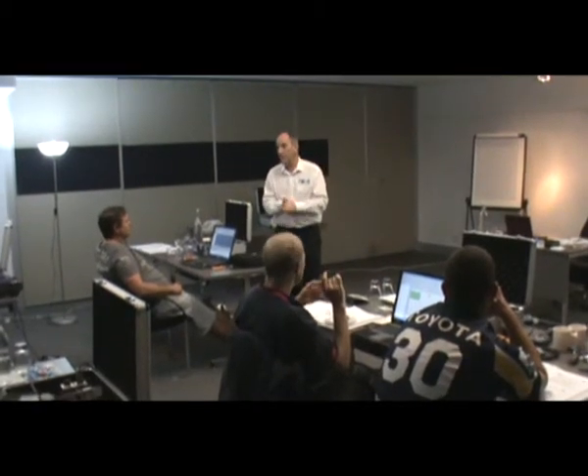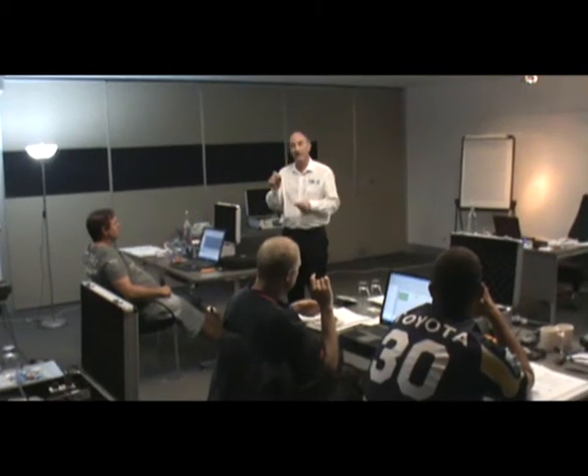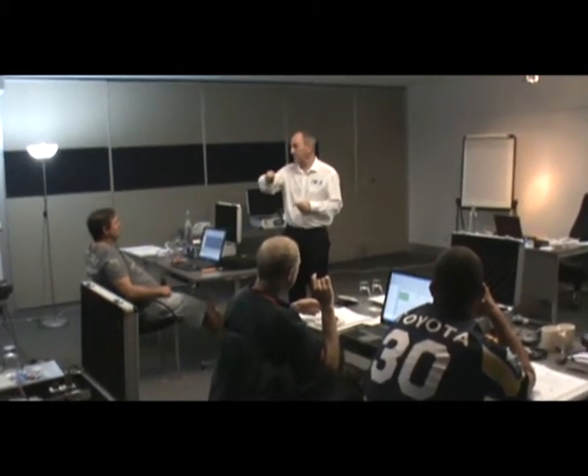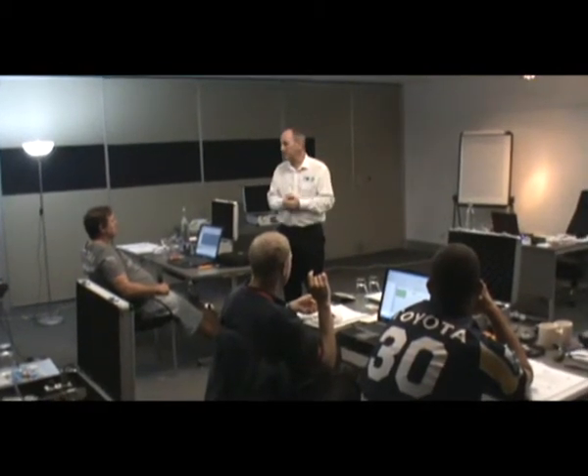The other thing to watch out for is loose terminals, of course. You can quite easily get a terminal on a power supply that's not been screwed up. And a little bit of vibration causes the devices to fall off. It's the same symptom.